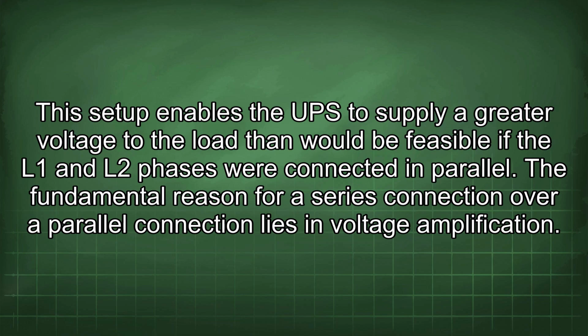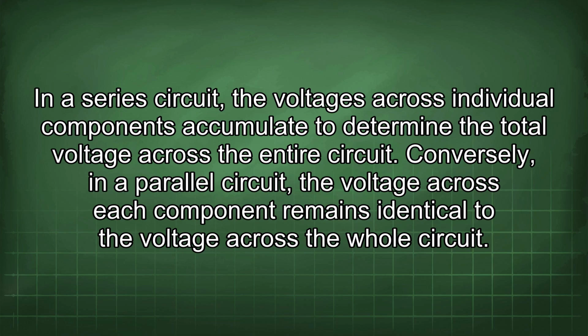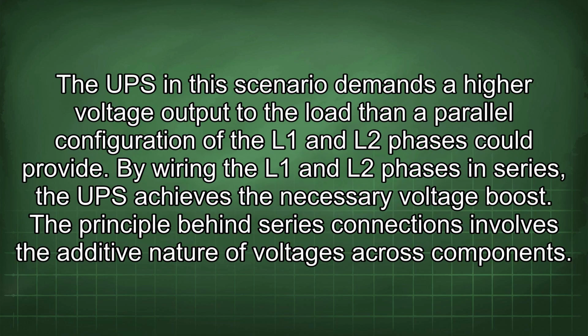The fundamental reason for a series connection over a parallel connection lies in voltage amplification. In a series circuit, the voltages across individual components accumulate to determine the total voltage across the entire circuit. Conversely, in a parallel circuit, the voltage across each component remains identical to the voltage across the whole circuit. The UPS in the scenario demands a higher voltage output to the load than a parallel configuration of the L1 and L2 phases could provide. By wiring the L1 and L2 phases in series, the UPS achieves the necessary voltage boost.